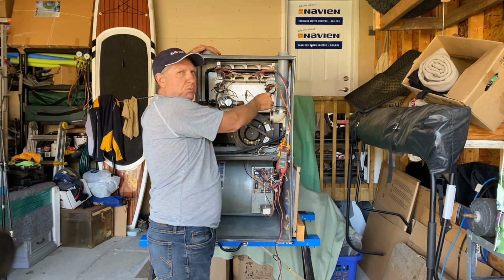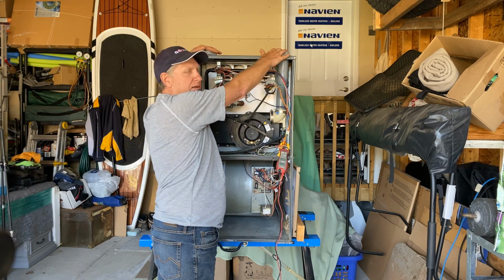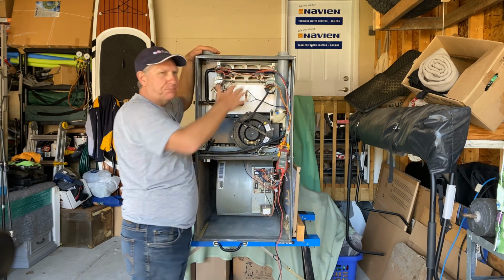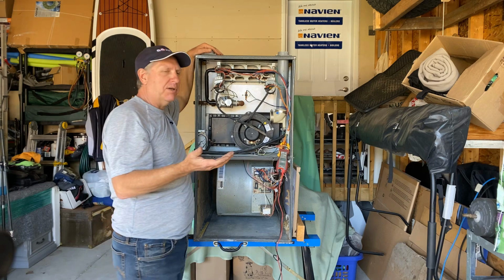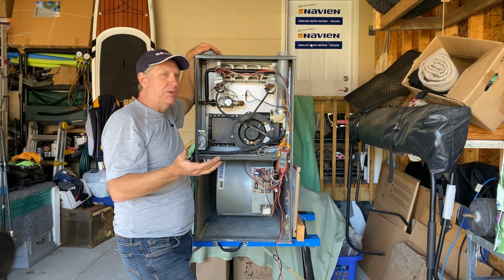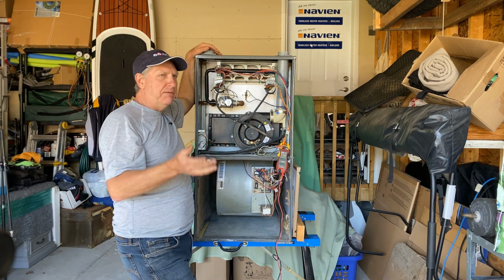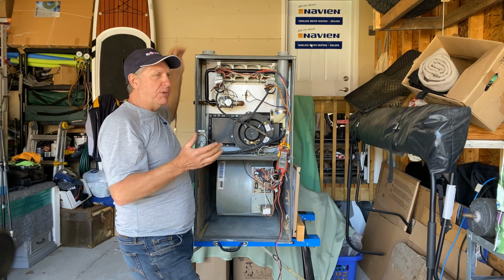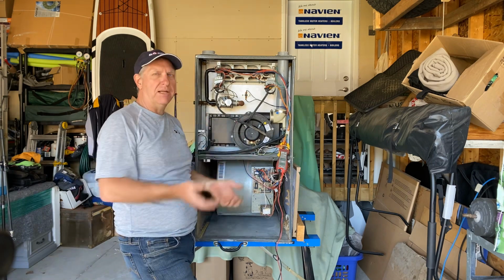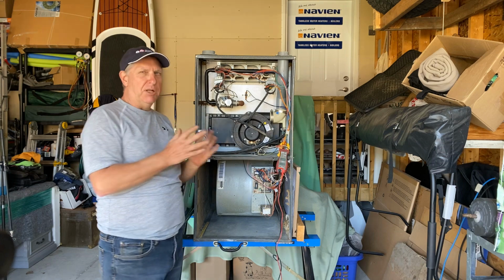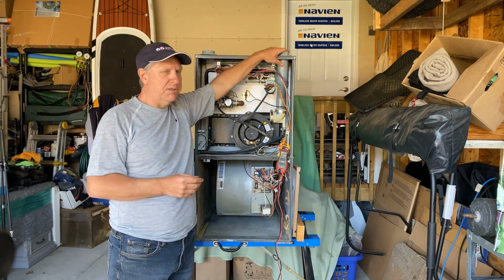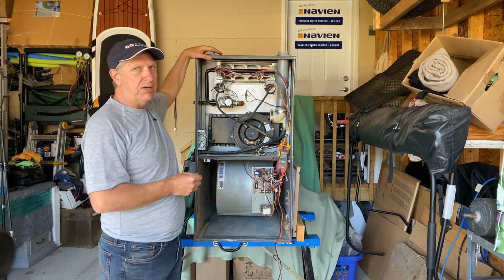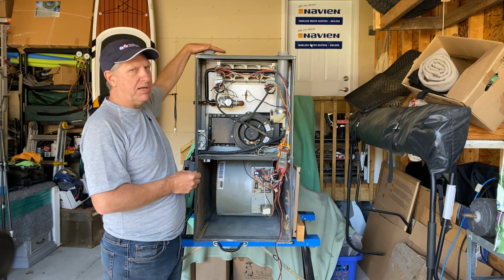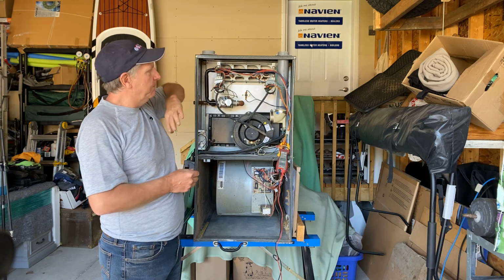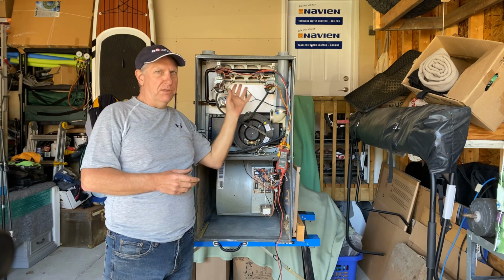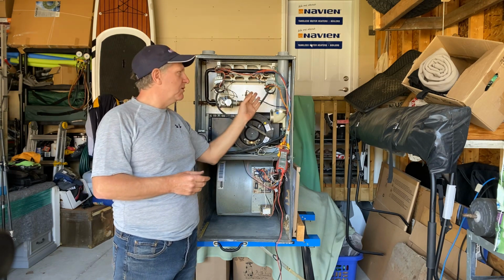These pressure switches will sense that there's something wrong here, and it does happen. They get frost build up in the wintertime, animals build nests in them. I've seen them with leaves in them. I've seen pretty much everything. People put furniture and stack them up against the vent pipes, plug them up. This has to exhaust. This has to suck air in. If not, your combustion process isn't going to work properly.